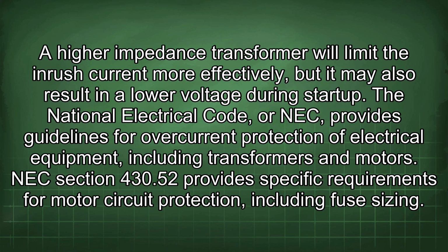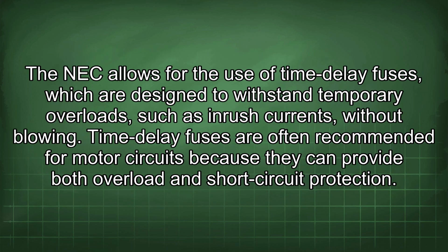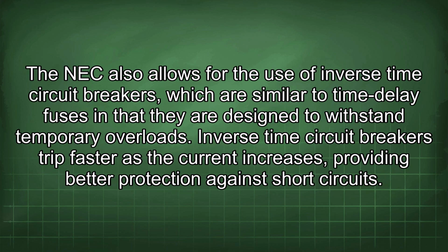The National Electrical Code, or NEC, provides guidelines for overcurrent protection of electrical equipment, including transformers and motors. NEC Section 430.52 provides specific requirements for motor circuit protection, including fuse sizing. The NEC allows for the use of time delay fuses, which are designed to withstand temporary overloads such as inrush currents, without blowing. Time delay fuses are often recommended for motor circuits because they can provide both overload and short circuit protection. The NEC also allows for the use of inverse time circuit breakers, which are similar to time delay fuses in that they are designed to withstand temporary overloads. Inverse time circuit breakers trip faster as the current increases, providing better protection against short circuits.